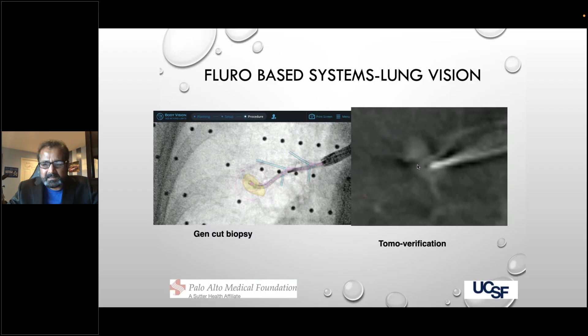Furthering the evolution of peripheral navigation, one of the significant drawbacks of superDimension for those of us who have used it is that the locatable guide protrudes about 5 millimeters outside of the extended working channel. That is problematic because the needle that we use is about 8 millimeters long, and when you change a 5 millimeter distance when you acquire the target, that can be an issue for reaching the center of the target. So the modification that was made was to transfer the coil, the sensor in the locatable guide, to the extended working channel. So you have these double sensors, one at the tip of the locatable guide and the other at the tip of the extended working channel. And when you pull out the locatable guide, you still have alignment.